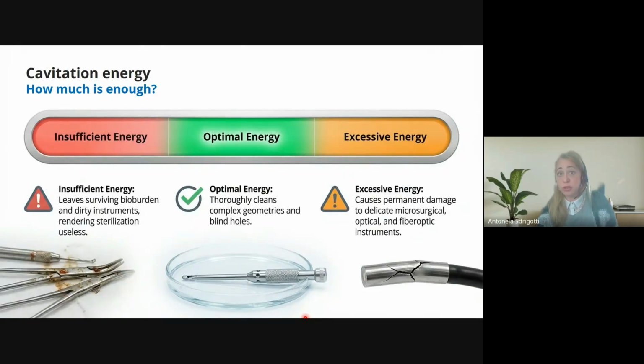So how much is enough? We are talking about energy. So how much is enough? So the optimal energy will be the one in the middle, of course, and it's the one that thoroughly cleans the complex geometries and blind holes without affecting the materials of the medical device that I'm trying to clean. So excessive energy is also a disadvantage because it can provoke permanent damage to our medical devices. Even more microsurgical, optical, and fiber optic instruments. Insufficient energy, of course, is something that we want to avoid because it leaves organic residues in our medical devices. Okay, so we need to find the optimal energy range to guarantee that our instruments are being correctly cleaned.